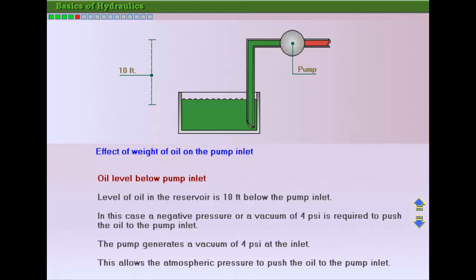Here, a negative pressure, or vacuum, equivalent to 4 psi, is required to push oil to the pump inlet. The pump must generate a vacuum of 4 psi at the inlet to allow atmospheric pressure to push the oil to the pump inlet.